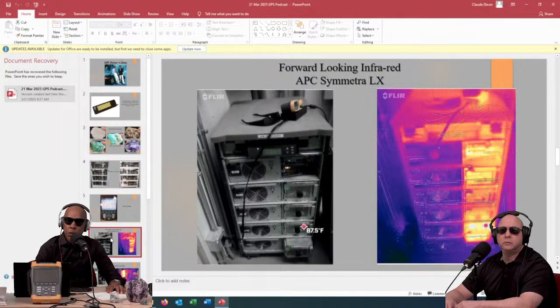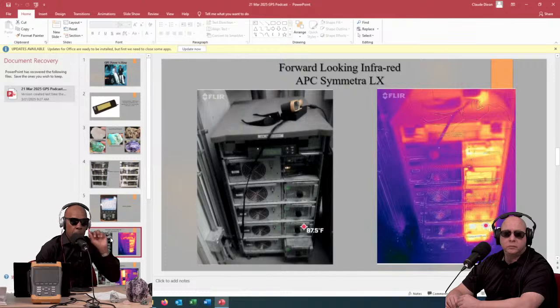With batteries, the spec is 77 degrees plus or minus 5. That's theoretically what you should keep your batteries at, but these are way beyond that. Fortunately these modules are self-contained, so I don't see a fire issue, but we do see swelling, where the batteries swell up inside the module, and getting them out takes almost an act of God.